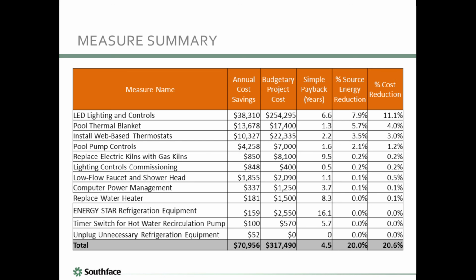Internet-accessible thermostats provide remote management. You can adjust schedules and set points as necessary from any location with any device that has an internet connection. You can also do event scheduling, so you can override the default schedule and set points for holidays, rentals, and other events that are known in advance. You can also configure alerts.